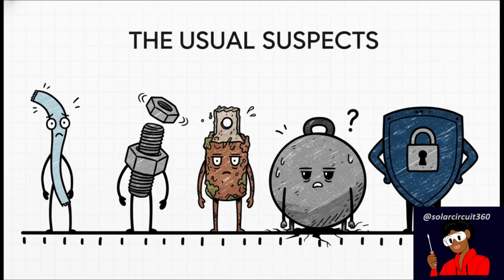We're talking undersized cables that just can't handle the flow, loose hardware at the connection points, corroded lugs that add massive friction, excessive load demands that outpace your system's design, or even modern lithium battery management system lockouts. These are your rogue resistors. Think of them like kinks in a garden hose, completely choking off the flow of water. They steal your voltage, and then they cause the inverter to throw a fault code.